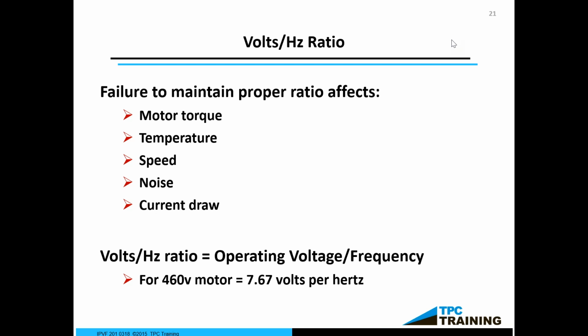If you think you have voltages on the bearing, take some readings. If someone says you have induced voltages in the bearings, the best thing to do is take a reading and see if it's for sure. A lot of people say that's happening, but then you don't see it. There are a lot of opinions on it, and I've seen it once or twice in 30 years, maybe three times. I think there's more talk than actual phenomenon with that one.